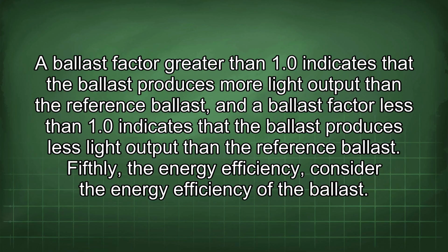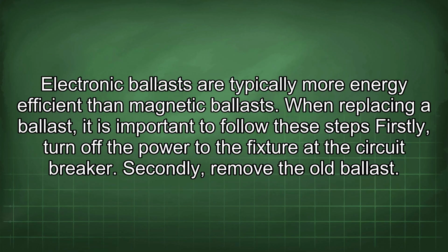Fifthly, the energy efficiency. Consider the energy efficiency of the ballast. Electronic ballasts are typically more energy efficient than magnetic ballasts. When replacing a ballast, it is important to follow these steps. Firstly, turn off the power to the fixture at the circuit breaker. Secondly, remove the old ballast.